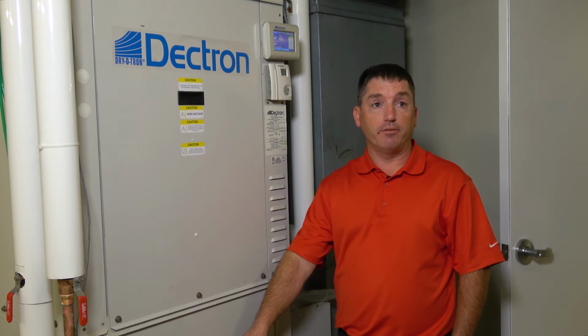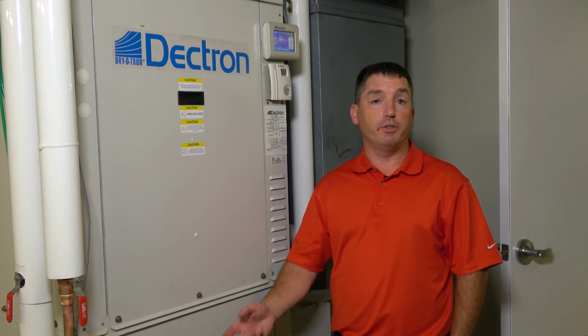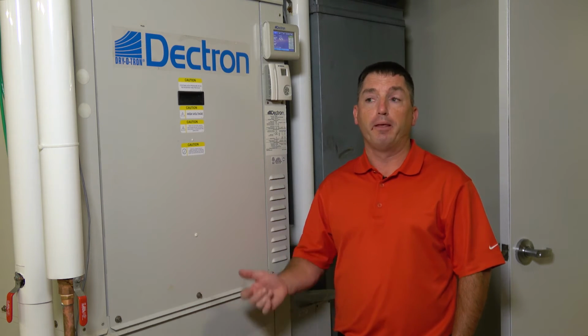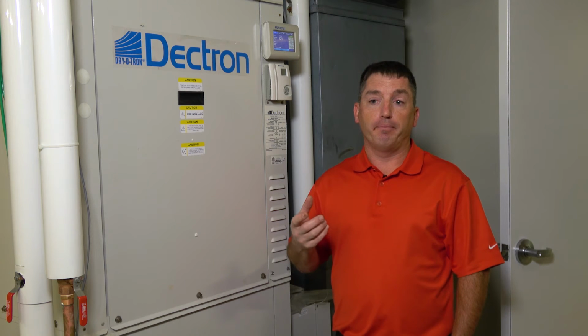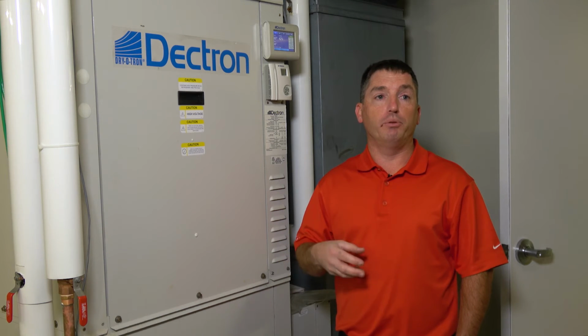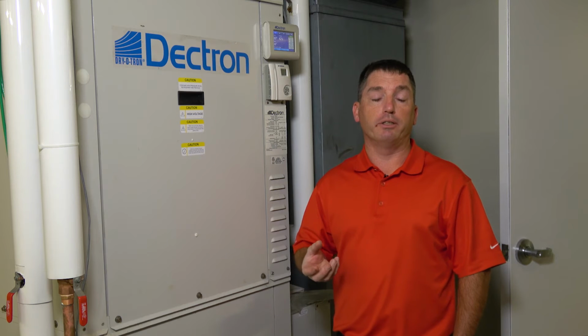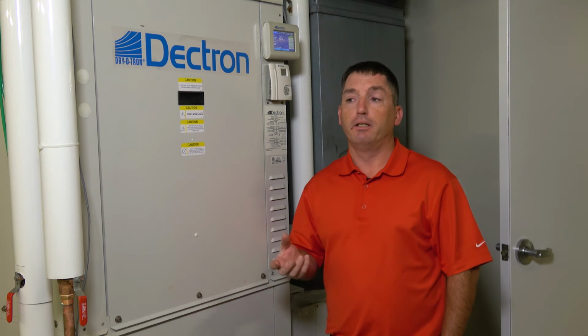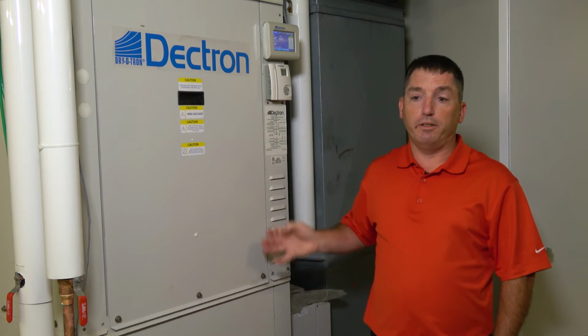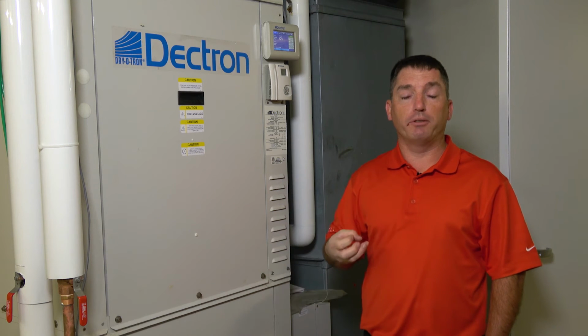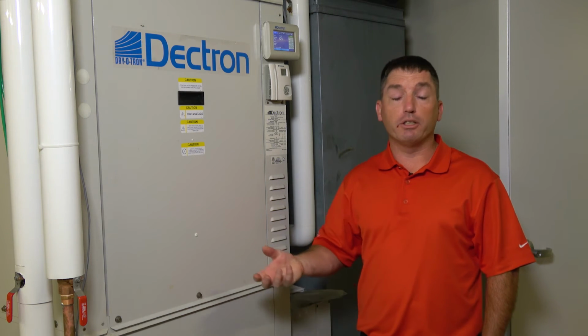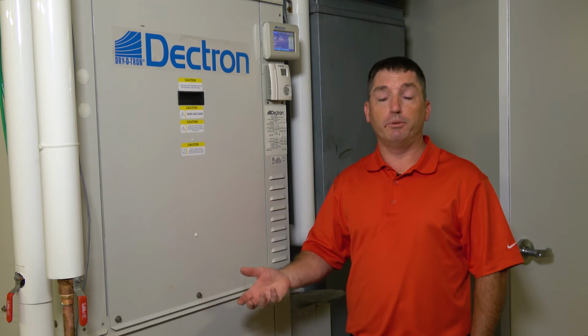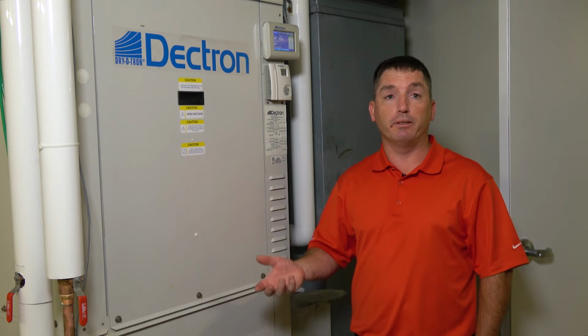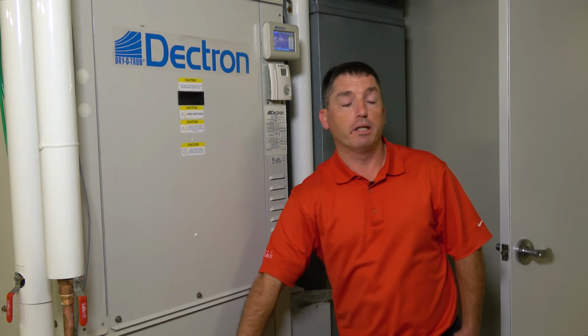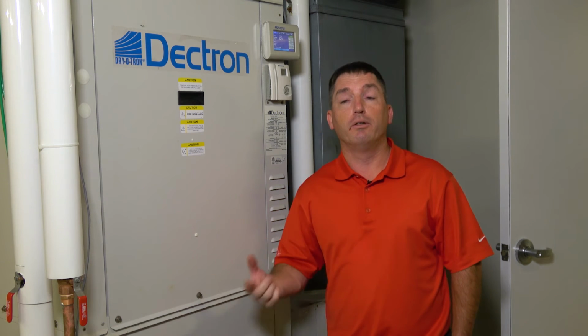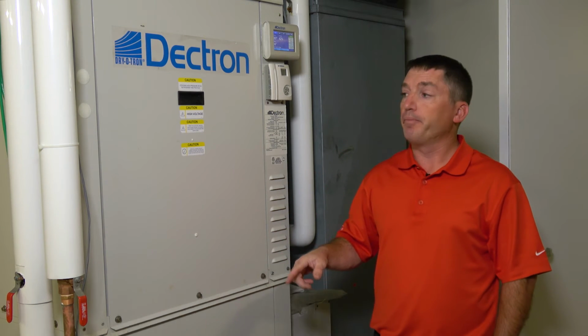We also have another heat exchanger that we circulate the pool water through. Anytime, in order to have evaporation, the pool has to lose energy in the form of heat. So once we've dehumidified, we've captured that energy. The logical place to put it back to is the pool water, because that's where it came from in the beginning. So like I say, we have a coaxial heat exchanger. We're always circulating pool water through.